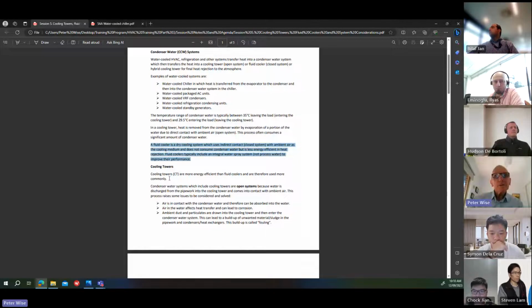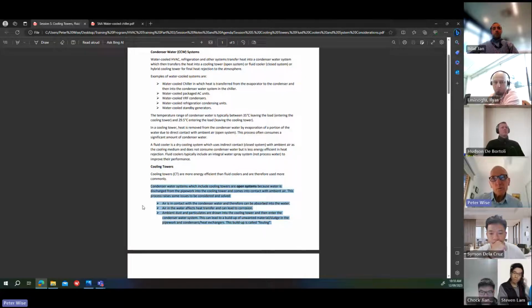Okay, so cooling towers are more energy efficient than fluid coolers and are therefore used more commonly. Condenser water systems, which include cooling towers, are open systems, as I said, because water is discharged from the pipework into the cooling tower and comes into contact with the ambient air. This process raises a few issues to be aware of and solved. Ambient air is in contact with the condenser water and is absorbed into the water. Air in the water affects heat transfer and can lead to corrosion. So you're getting oxygen into the water, and it becomes corrosive.